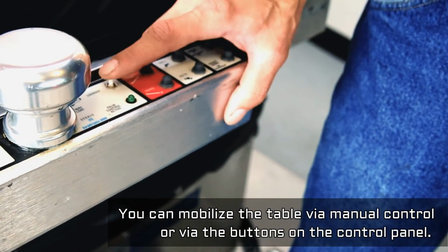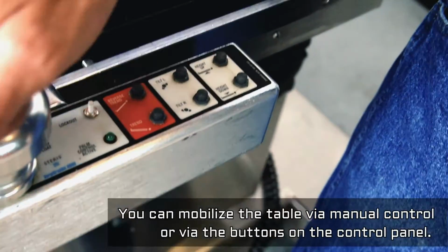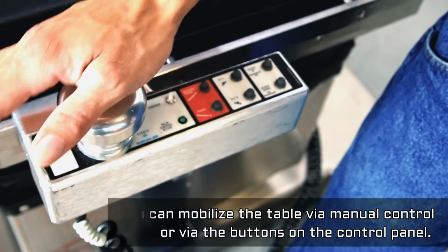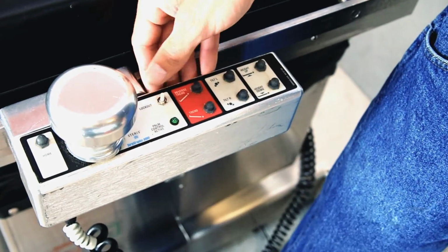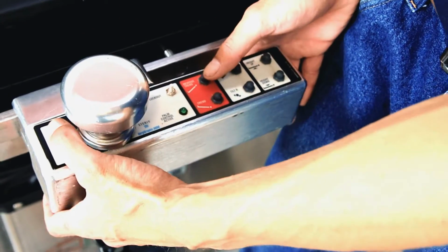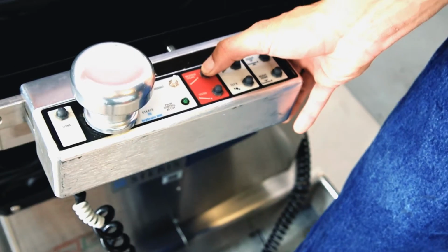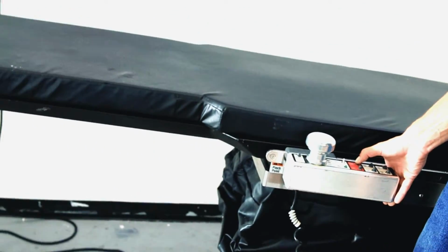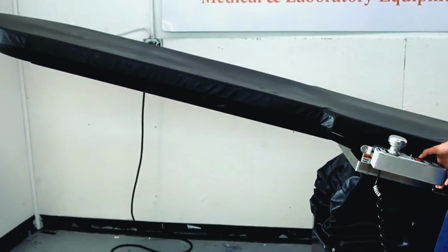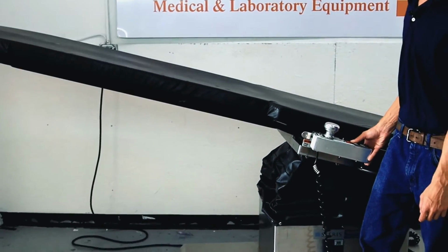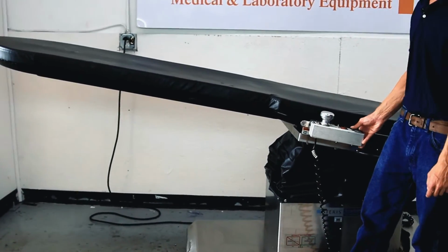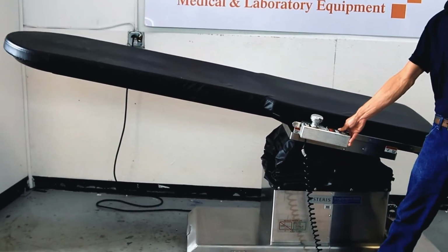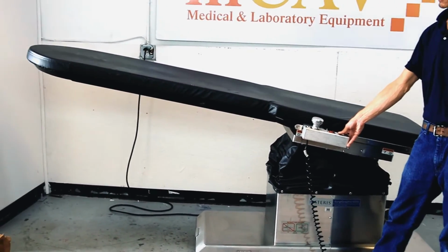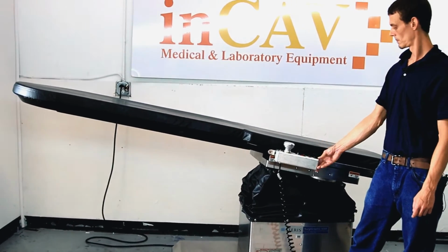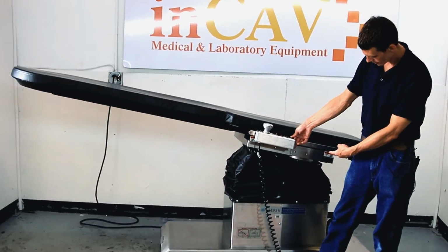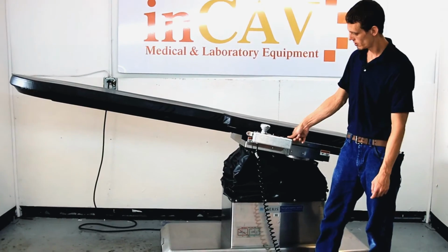We have a lockout button that will allow you to actually use the hand control, or the knob. You want to keep that unlocked to move the machine, and then all you have to do is press the button. This is going to trend upward. And we'll go back down. We got our tilt to both left and right. We have our height, of course, as you can see, up and down.